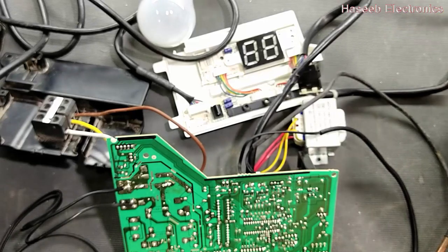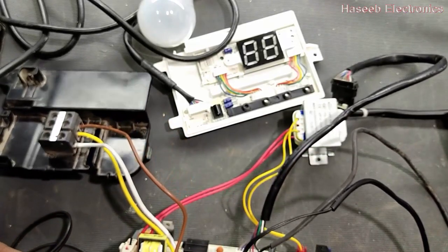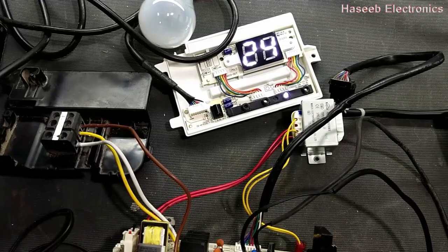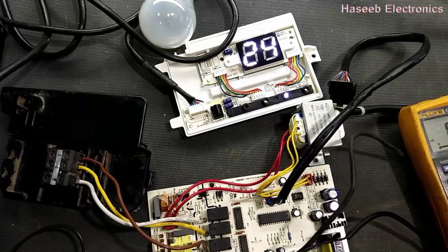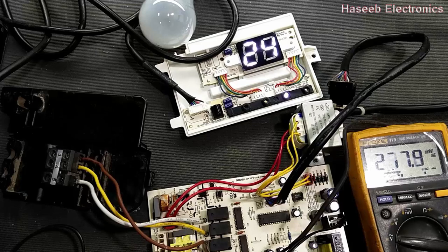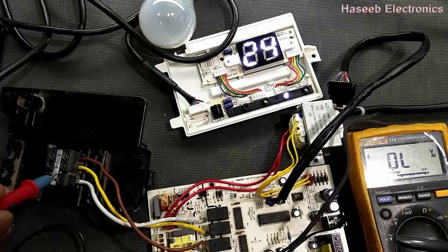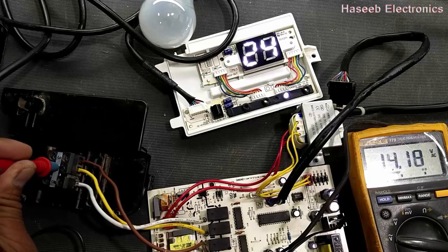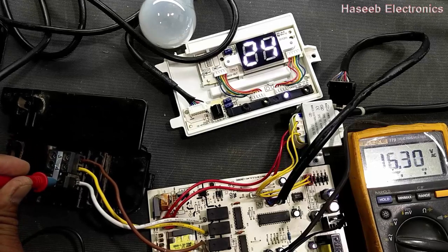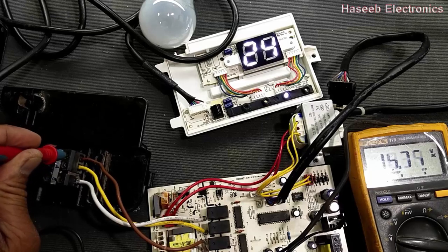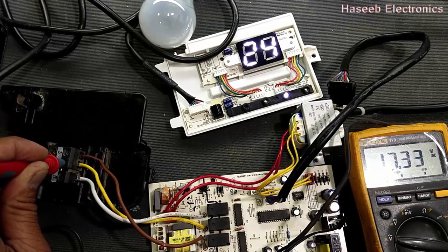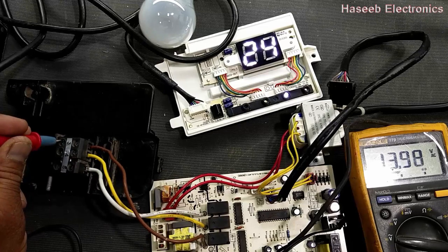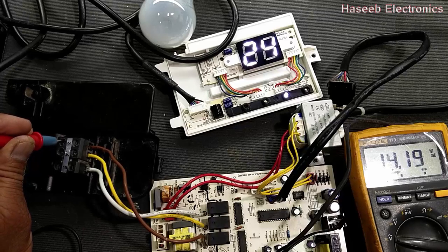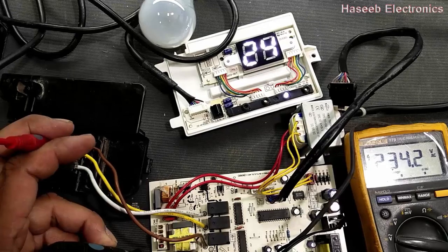Wow, it is turned on. I have to push the reset button. So it is turned on. So this was the reason. And now we can check the voltage. Set the multimeter to AC. Connect at the common line. Still we don't have voltage output because it will take some time, because it has to wait for, I think, 3 minutes. In the first step we must find this voltage at the compressor pin.